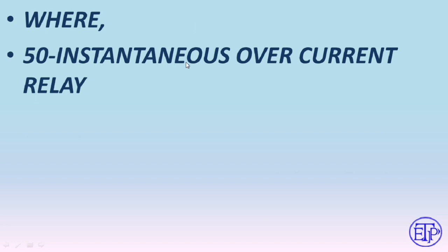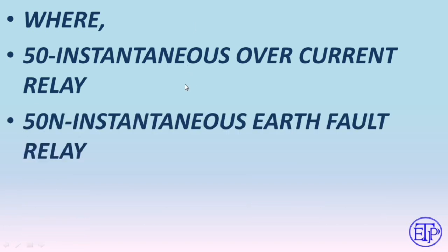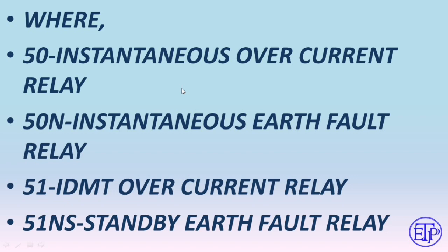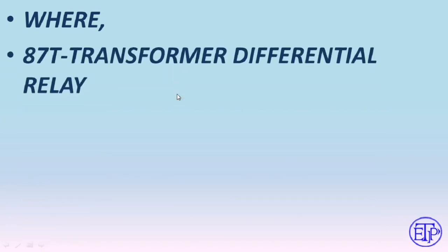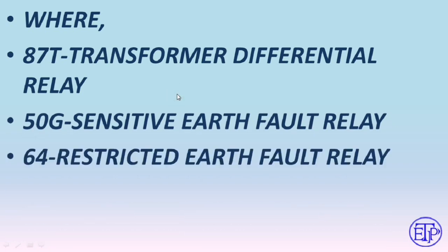Relay designations: 50 is instantaneous overcurrent relay, 50N is instantaneous earth fault relay, 51 is IDMT overcurrent relay, 51NS is standby earth fault relay, 87T is transformer differential relay, 50G is sensitive earth fault relay, and 64 is restricted earth fault relay.